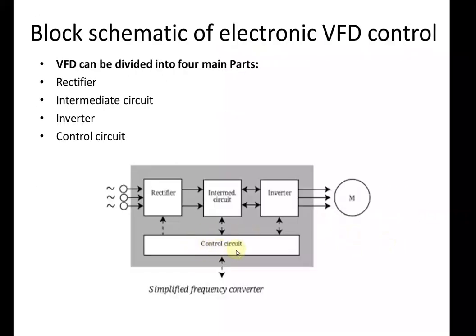The control circuit — also called the control card — is the fourth main component of the frequency converter or VFD. This control circuit is used for four different operations: first, control of frequency converter semiconductors; second, data exchange between the frequency converter and its peripherals; third, gathering and reporting fault messages from the inverter and intermediate circuits; and fourth, carrying out protective functions for the frequency converter and the motor.